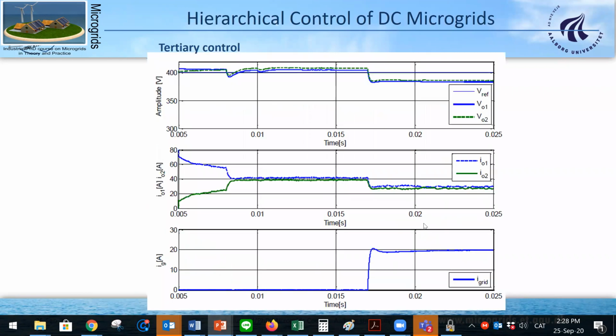What happened when we start the secondary control is we restore the voltage levels. Then if we start the tertiary control, we are also able to import power from the DC distribution grid—in that case, we imported 20 amps. Of course, you do that by decreasing the voltage level inside your grid.